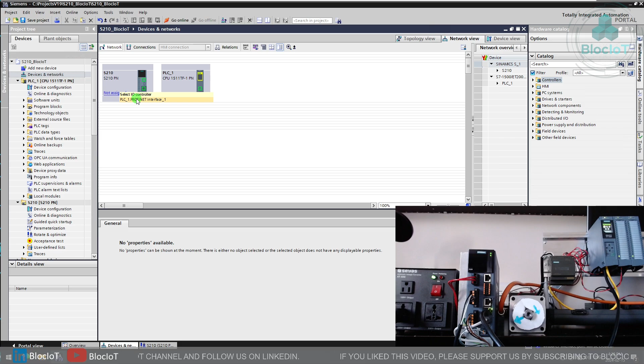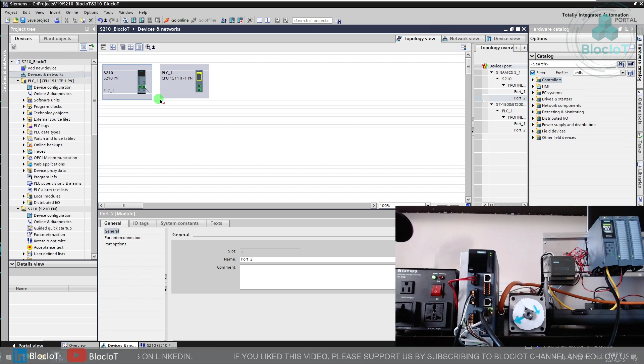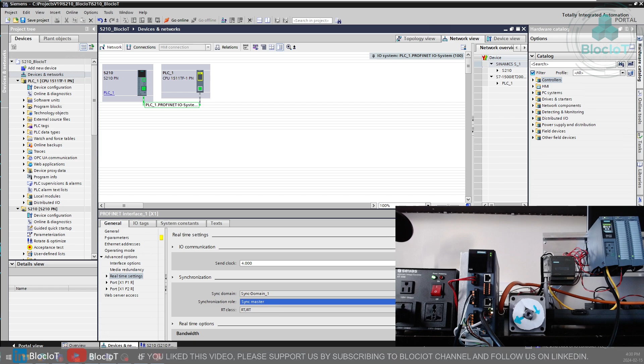We can just simply click on not assigned and select this PLC as the master controller, and you can also go to the topology view, as you may know in TIA Portal, and connect the right port, the right PLC port. There are just a couple of important settings that you need to do on the drive and also on the PLC side before you start doing the programming. The first thing on the PLC side, you just need to open the properties of your Profinet interface, go to the advanced options and real-time settings, and you need to define the role of your PLC. Here we just want to define it as sync master. That's the typical configuration when you are connecting a PLC to a drive. Just save your project, and that's all the settings that you need to do on the PLC side.